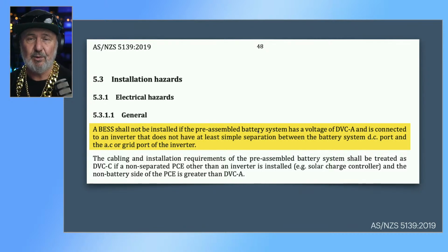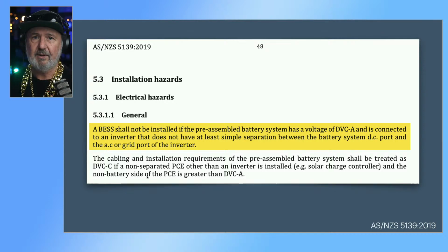Typically done by things like in a transformer, it's the varnish on the copper windings is simple separation. That's good enough because it's not providing, under normal conditions, not under fault, a direct path from primary to secondary on the transformer. So there you go. And also points out the cabling and installation requirements of the pre-assembled battery system shall be treated as DVC-C, i.e. equivalent to an LV, if a non-separated PCE other than an inverter is installed. So if you're installing, here, this is that reference to MPPT, so if you're installing an MPPT, which is a non-separated MPPT, then you have to treat that as DVC-C for all components on the battery side. Yep, so there you go. That's 5139.